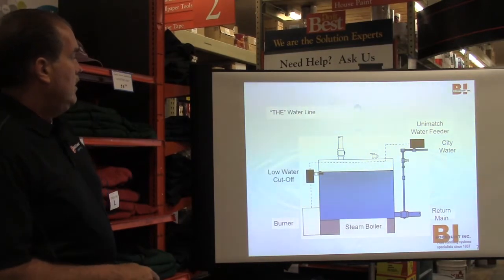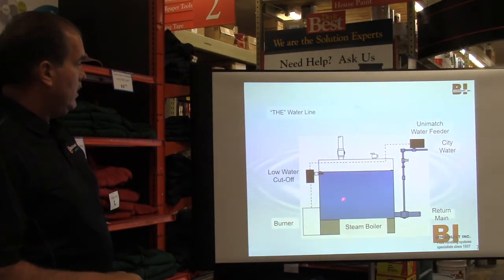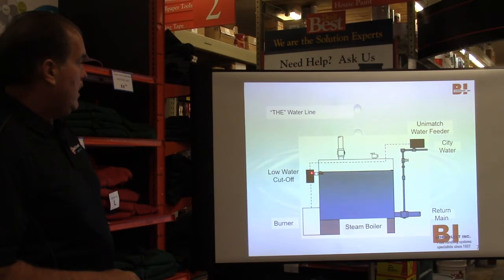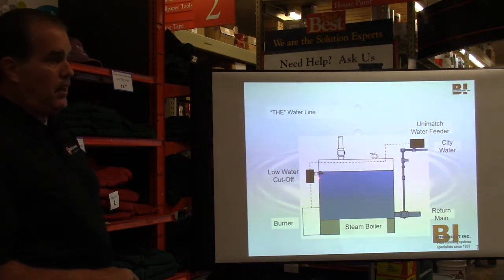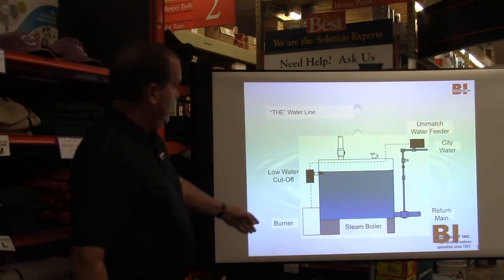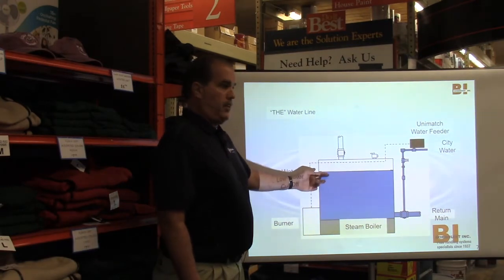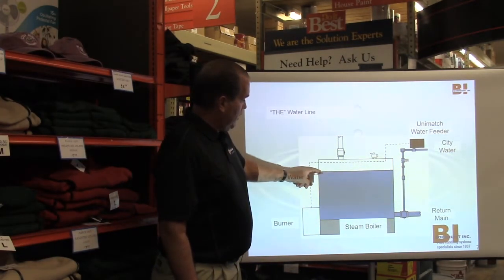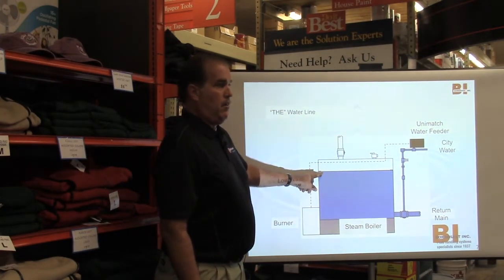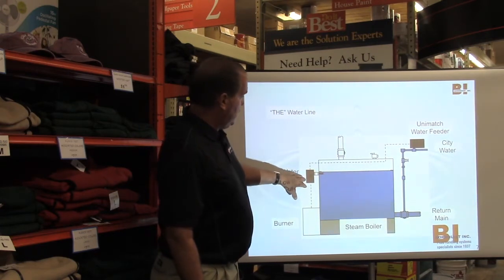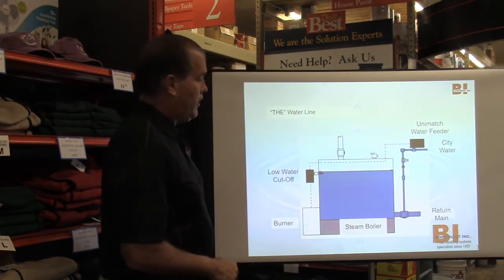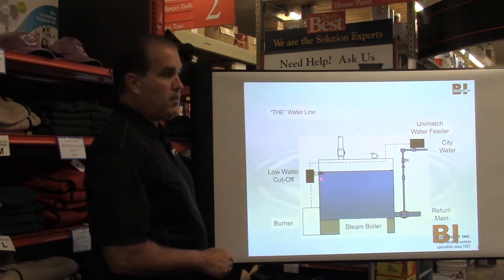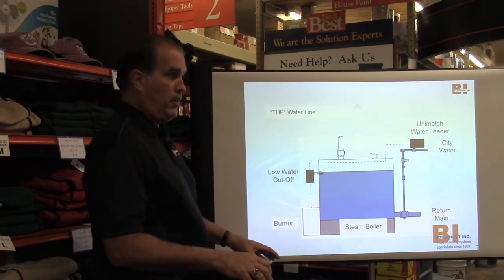Steam. This is a steam boiler. Here's the low water cutoff probe type that I was talking about. It's a little probe that actually sticks inside the heat exchanger. As the water level comes up and down, it senses the presence of water. In this case, the low water cutoff is wired to the burner. So if water drops off the probe, it shuts the burner off.